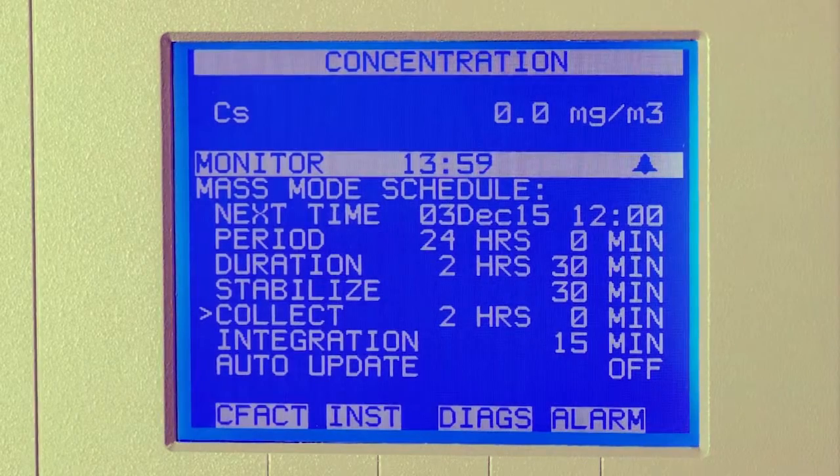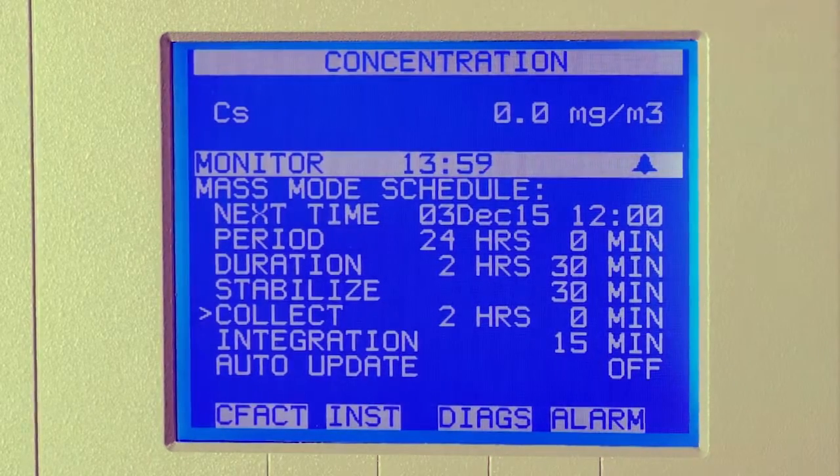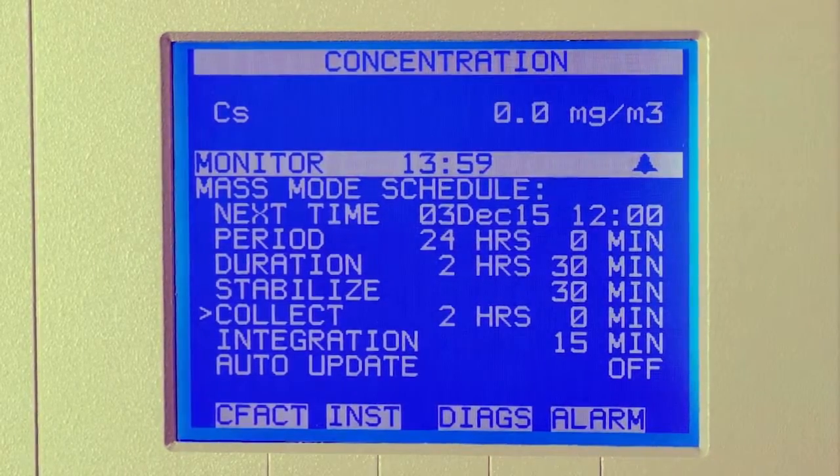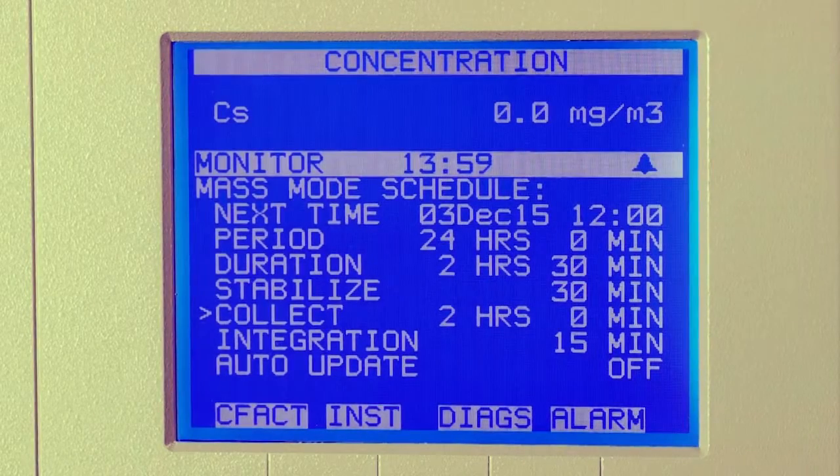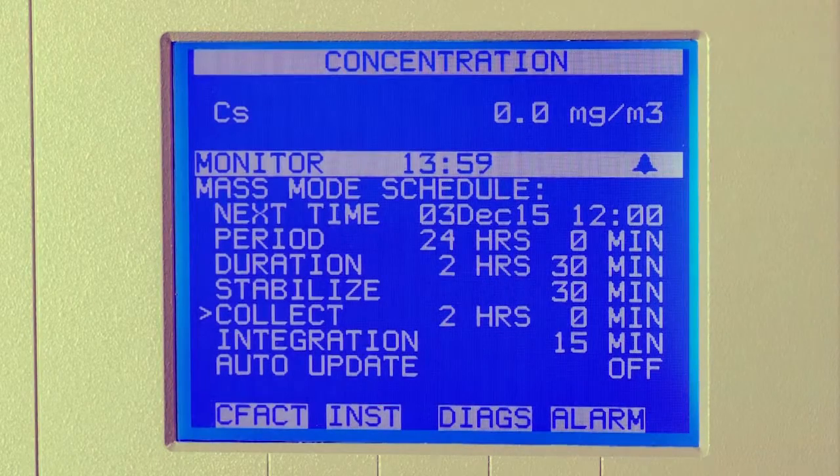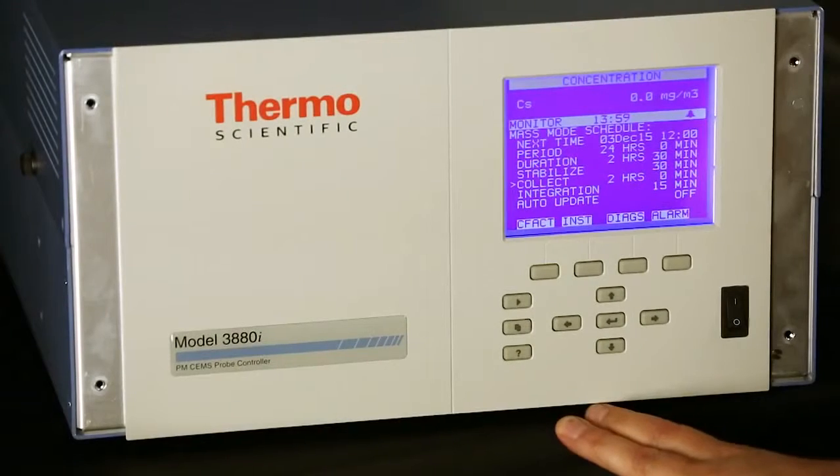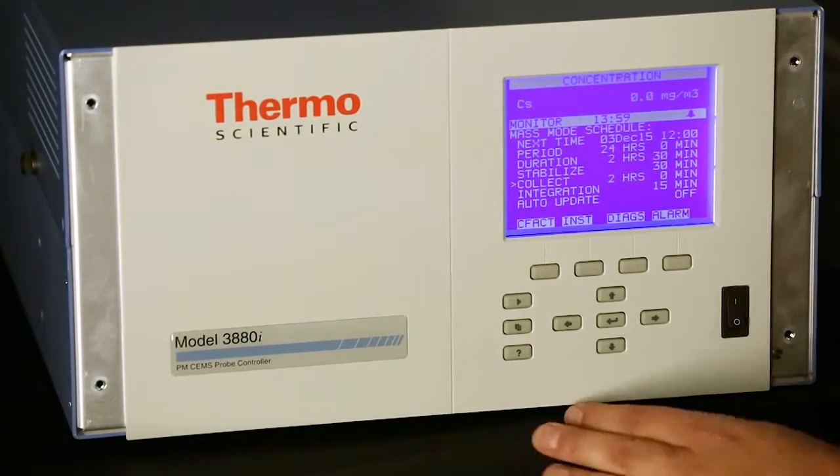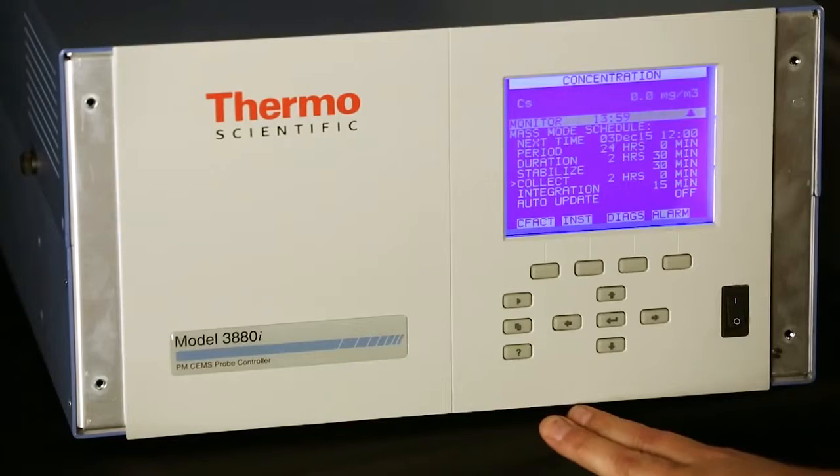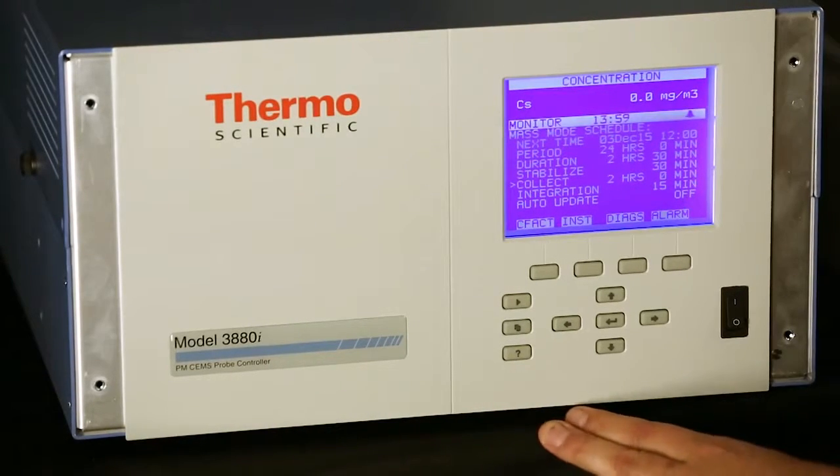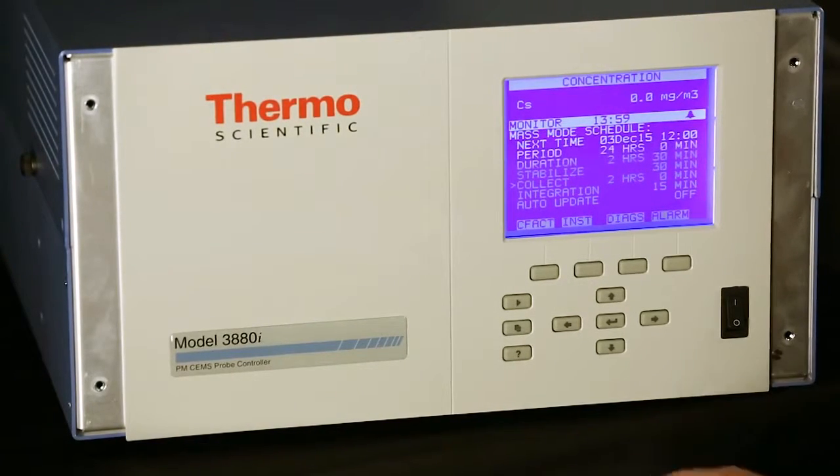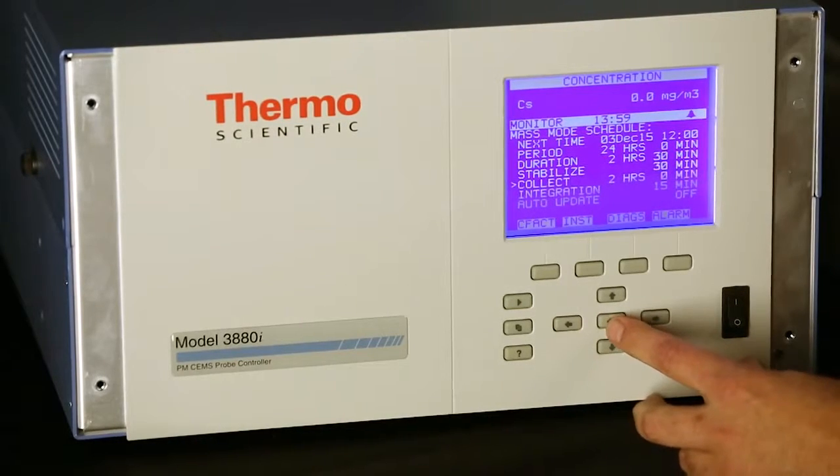Your minimum duration time to run a mass mode is two and a half hours. You can run it for longer if need be. In summary, set the instrument to 12 o'clock, two hours of collection, 30 minutes stabilization, keep the integration set at 15, then hit enter and you're set to go.